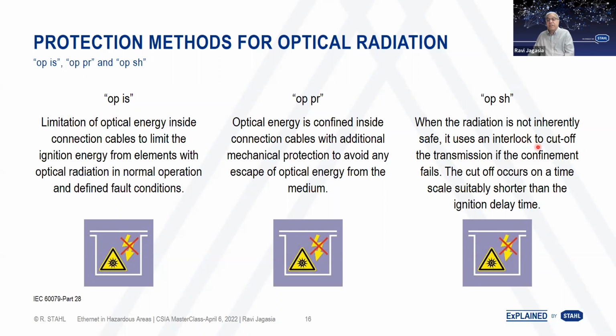This is an interlock to shut off the fiber optics. If the loop detects that there is an open or a short circuit, then from the source or both the sides, the receiver and the transmitter, the power or the optical energy is shut off for a suitable time and allows you to repair the problem and then restart the communication. So these were the various fiber optic protection methods or optical radiation protection methods, which evolved as one of the ways of transmitting Ethernet over hazardous area.